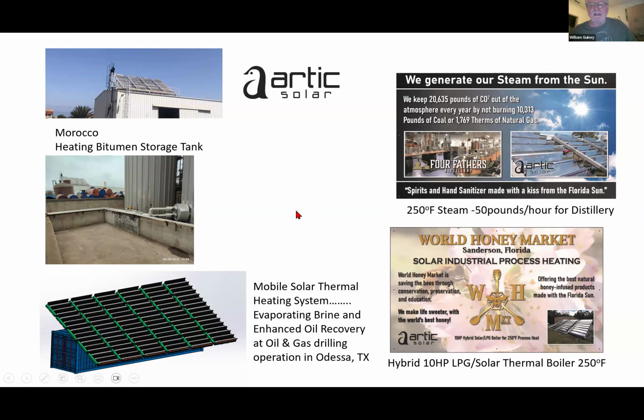And we were generating steam at a distillery. We're generating about 50 pounds of steam per hour. Most distilleries and breweries need at least 300, so this is a relatively small system, but he's very pleased with it. It's just installed in parallel. As we're providing steam into his main steam line, his boilers are on idle. When our solar production starts to decrease, his boilers increase and provide the energy necessary to maintain the pressures and temperatures going into the facility.